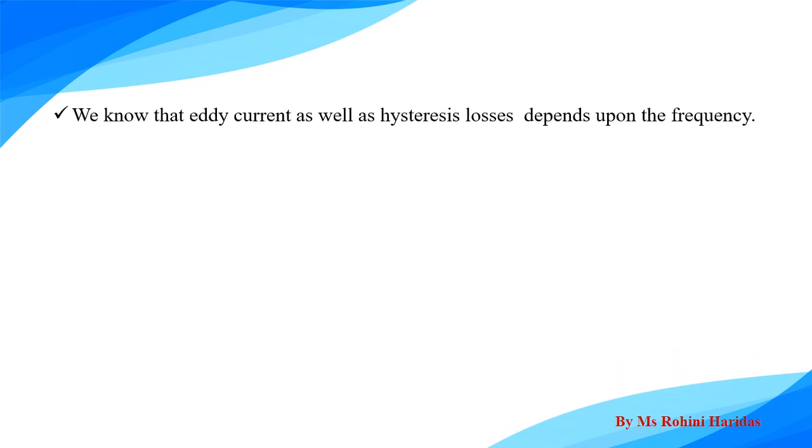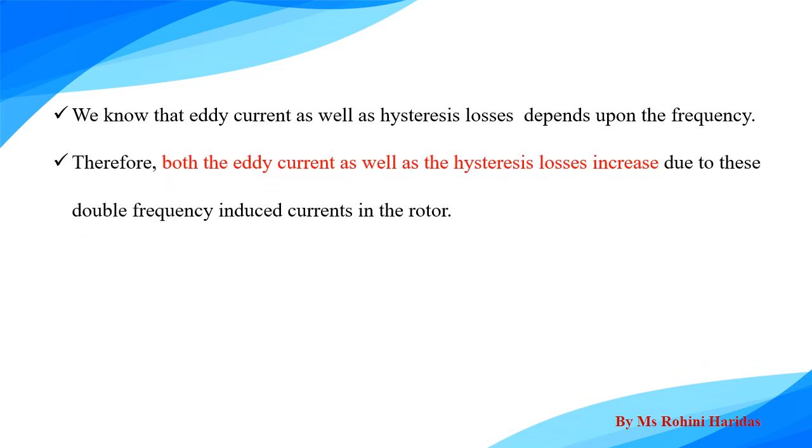This causes the double frequency current of a large amplitude to be induced in the rotor conductor. We know that the eddy current as well as hysteresis losses depends upon the frequency. Therefore, both the eddy current as well as the hysteresis losses increase due to these double frequency induced currents in the rotor. Thus, if the stator carries unbalanced currents, then it is the rotor which is overheated.